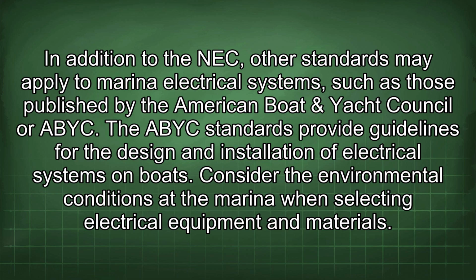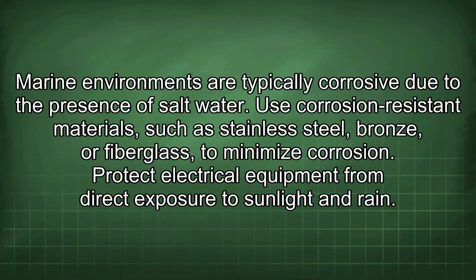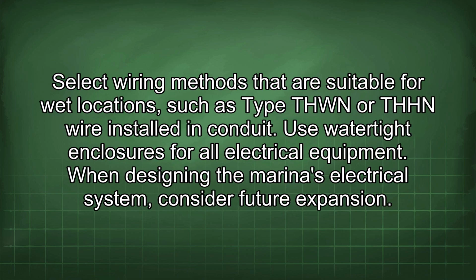Consider the environmental conditions at the marina when selecting electrical equipment and materials. Marine environments are typically corrosive due to the presence of salt water. Use corrosion-resistant materials such as stainless steel, bronze, or fiberglass to minimize corrosion. Protect electrical equipment from direct exposure to sunlight and rain. Select wiring methods that are suitable for wet locations, such as type THWN or THHN wire installed in conduit. Use watertight enclosures for all electrical equipment.